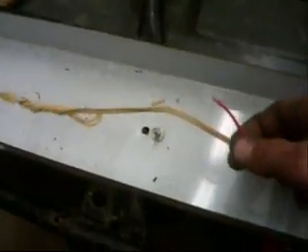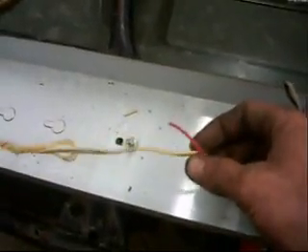The actual wiring is a little bit different on this one. With the two blue wires on this T8 ballast, you're going to take one and connect it to one socket on this end, and then this other one you don't need, so you can either take it out from the socket or cap it off — we'll just cap it off. Then you're going to take one blue and connect it to one blue on this end and cap it off. The common side is red on the T8, so we're going to connect it. We can connect it to one or both — it doesn't matter, because they both go to the same terminals.